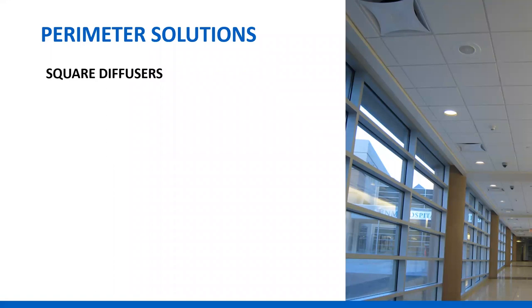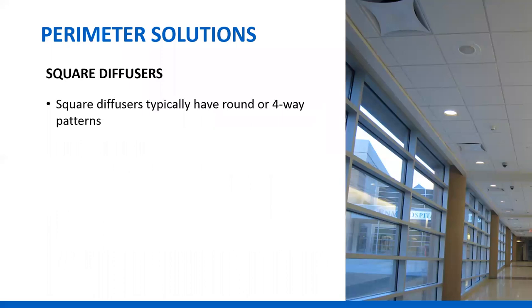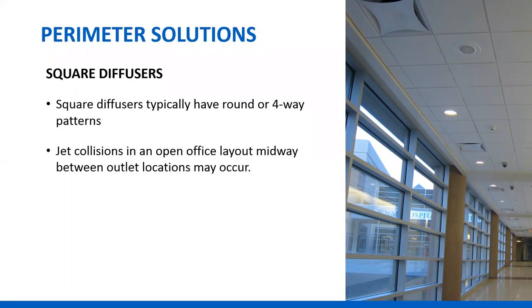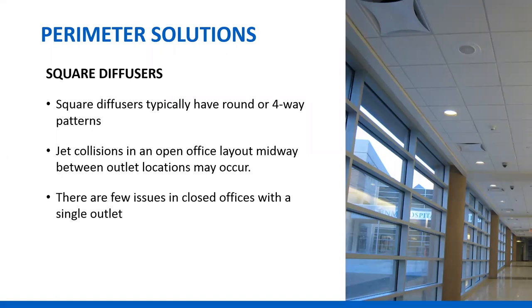Often we see square four-way blow diffusers. In this example, they're located offset close to the wall. This is required if you want to get the heating airflow to reach down into the occupant zone enough to offset the cold air spilling down the window. One of the things that happens is you may get some collisions at the midpoint between diffusers — it may be ideal to not have anyone sit at the midpoint. I always recommend that the perimeter zone be a corridor so that people don't have to sit next to the window.